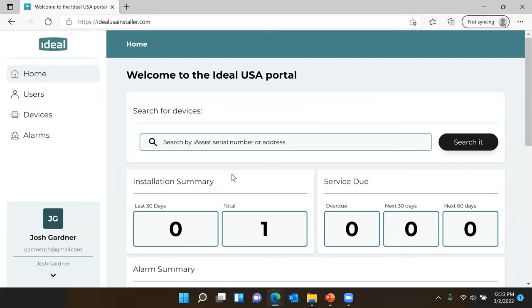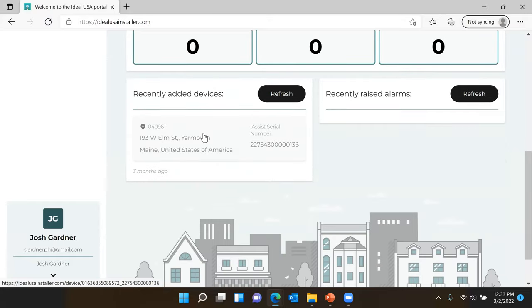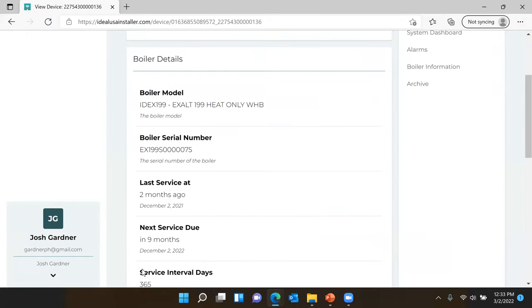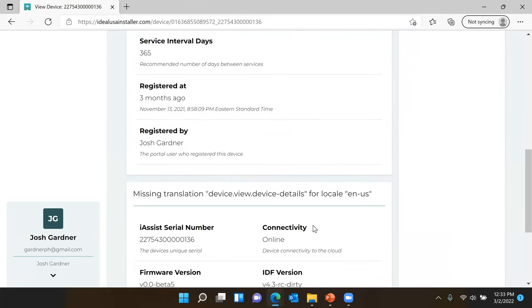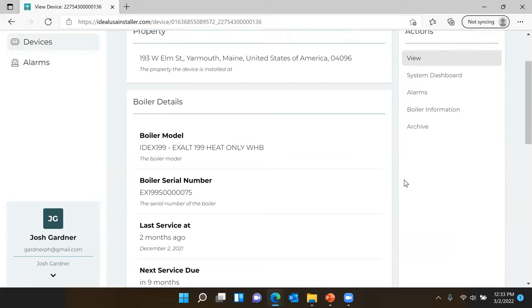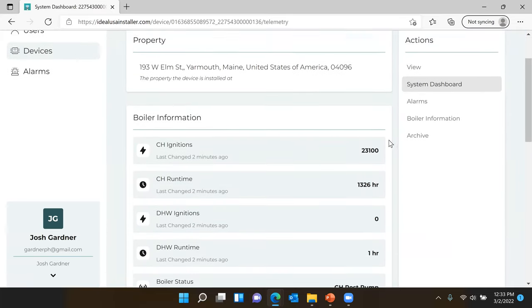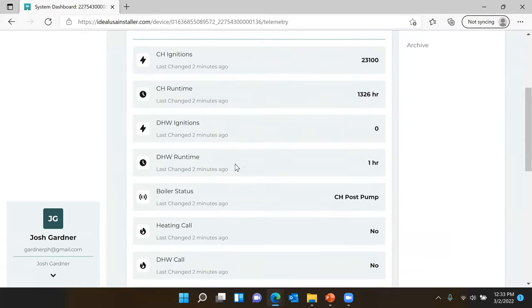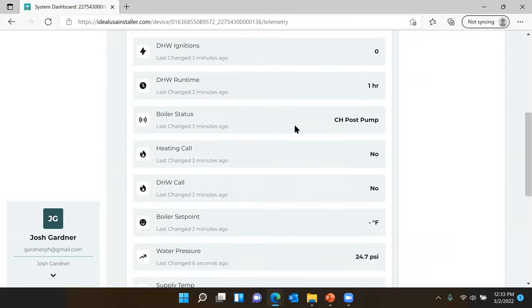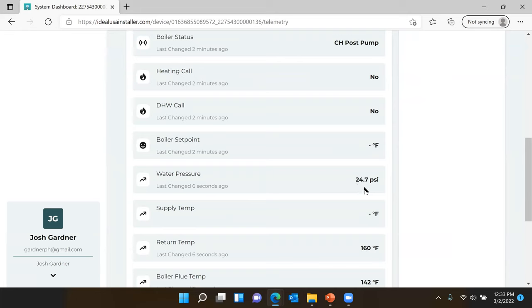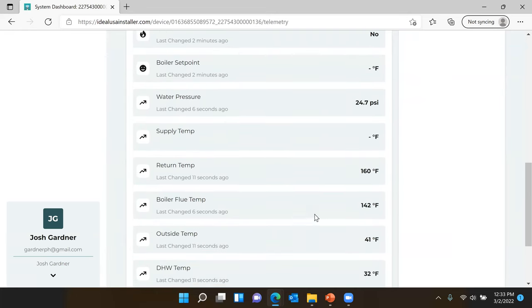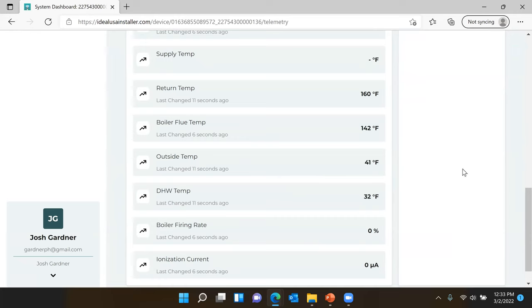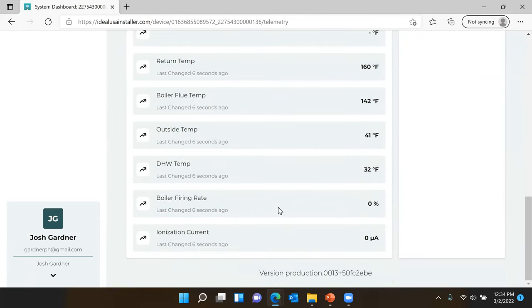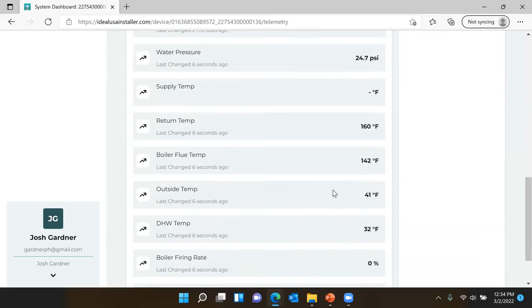So you can go in and look at all your ignitions. It has your boiler information, your serial number, service, and everything that's going on. But if we go into our system dashboard, I can see all my ignitions, my runtime, DHW ignitions. Obviously, I don't have anything for my domestic hooked up to my boiler. What my boiler is doing right now, my water pressure in live time, supply and return temps, boiler flue temps, my outside temperature, 41 degrees up in Maine right now. That's nice out there. Firing rate and my ionization current.